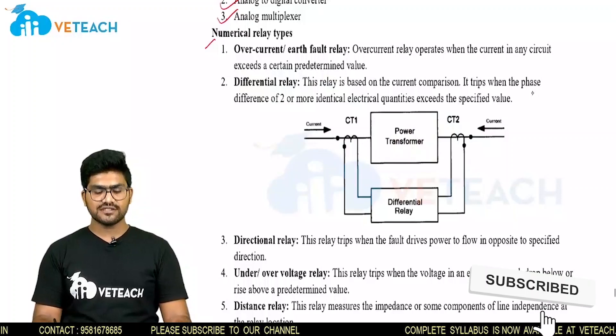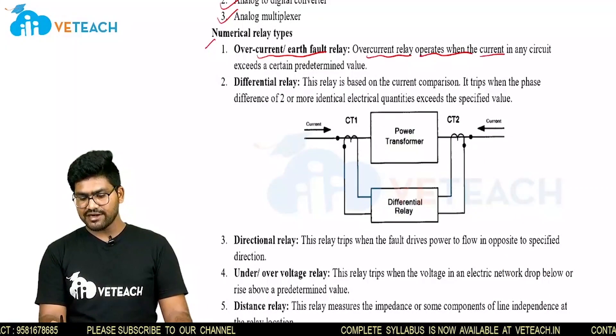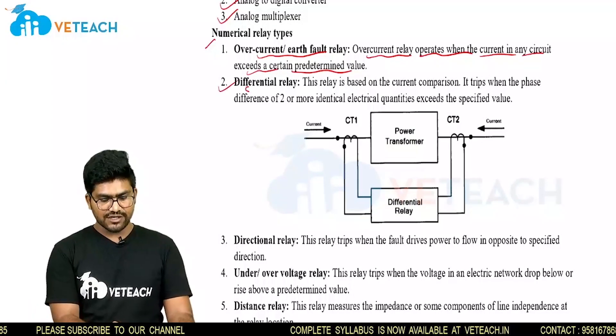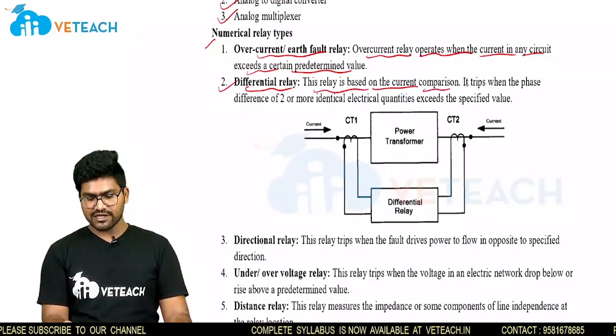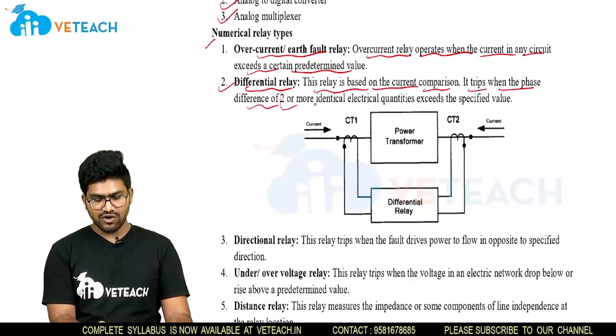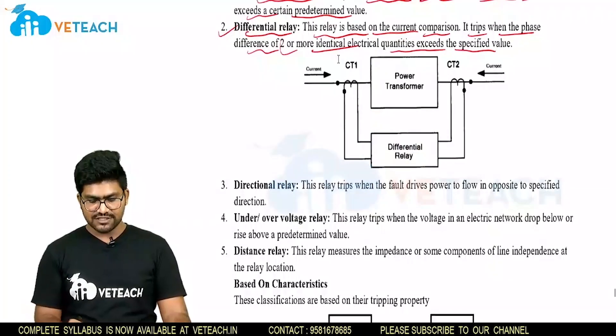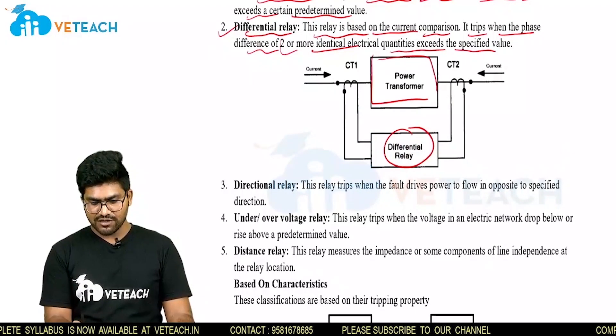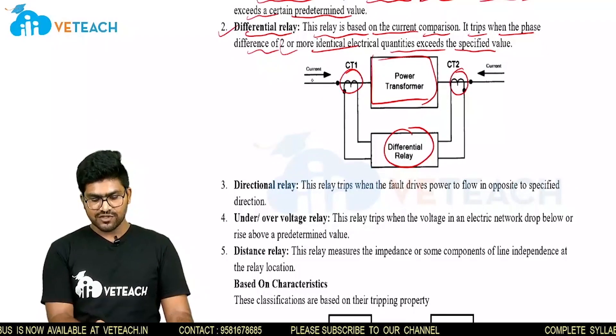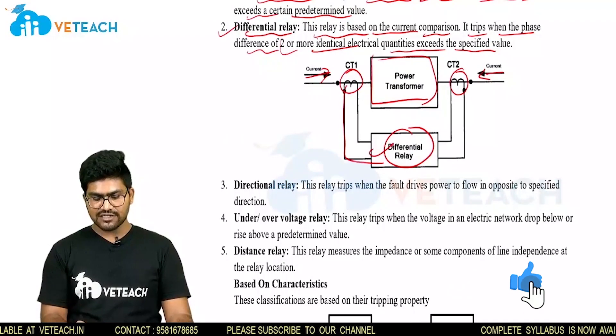There are different types of numerical relays. The first is overcurrent and earth fault relay — an overcurrent relay operates when the current in any circuit exceeds a certain predetermined value. Next is the differential relay, which is used based on current comparison. It trips when the phase difference of two or more identical electrical quantities exceeds the specified value. To connect the differential relay, on a power transformer the primary side has CT1 and the secondary side has CT2. Current enters from both sides, and between these two CTs the differential relay is connected.